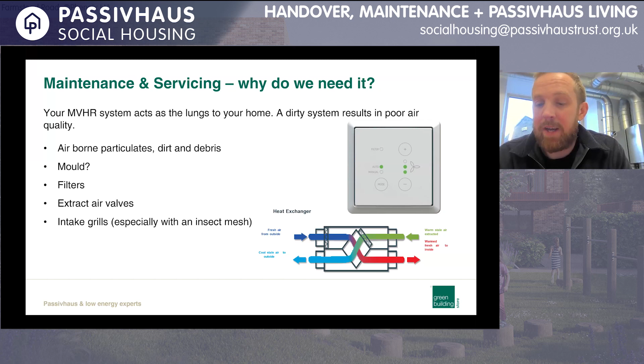And intake grills. So we often get called out to MVHR systems that aren't ventilating, and that could be quite a problem. However, when we get there, it's typically the intake grill bringing air in from outside, especially if it's got an insect mesh in there. We actually remove those now. If the grills are accessible, you could keep the insect mesh in, but someone does need to know to go around and give that a clean.